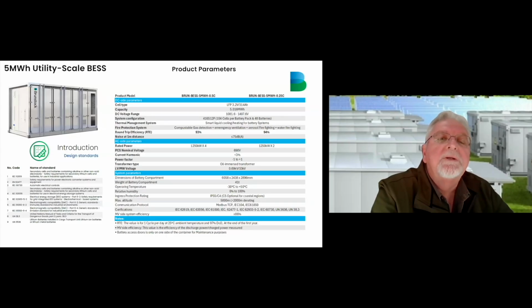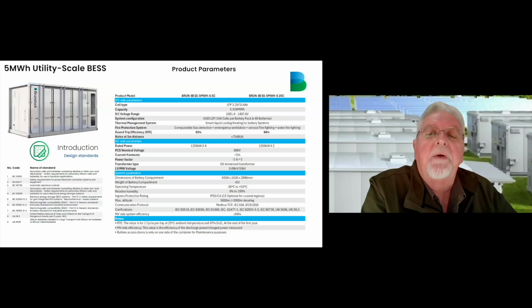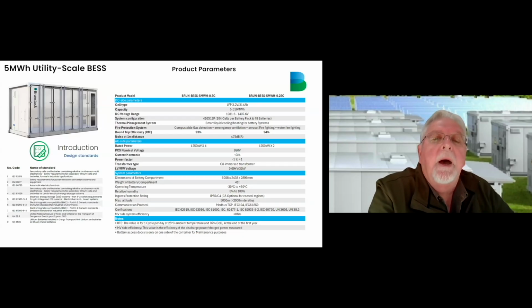You'll see the round trip efficiencies here of the two configurations. 0.5C is 93% and 0.25C is 94%, due to the fact that different cells are used. On the AC parameter side, on your 0.5C base system, you can connect 4 1.25 megawatt PCSs, and on the 0.25C, you can connect 2 1.25 megawatt PCSs. AC voltage of the PCS is 690 volt, and it will step the voltage up on the step-up transformer from 690 volts to 11, 22, or 33 kV.